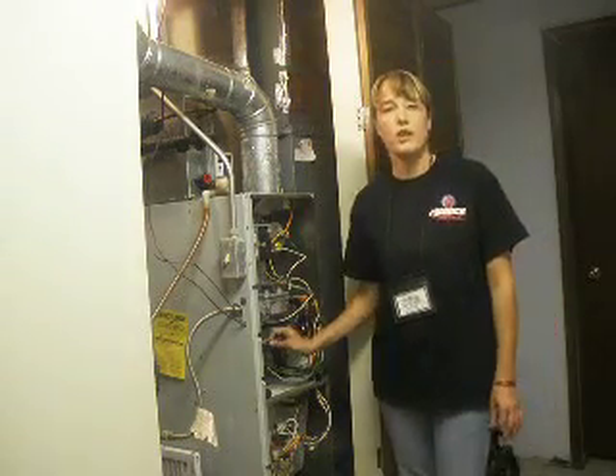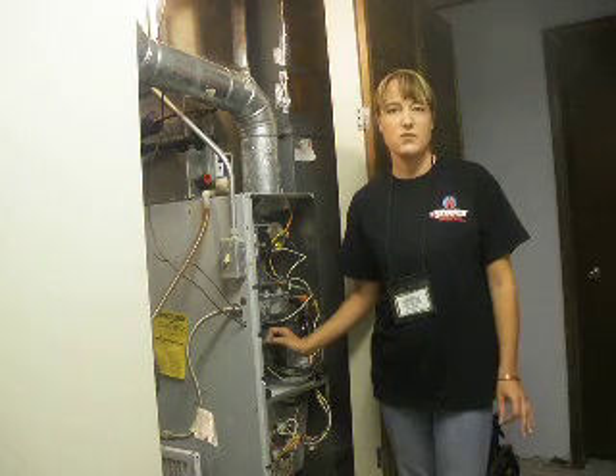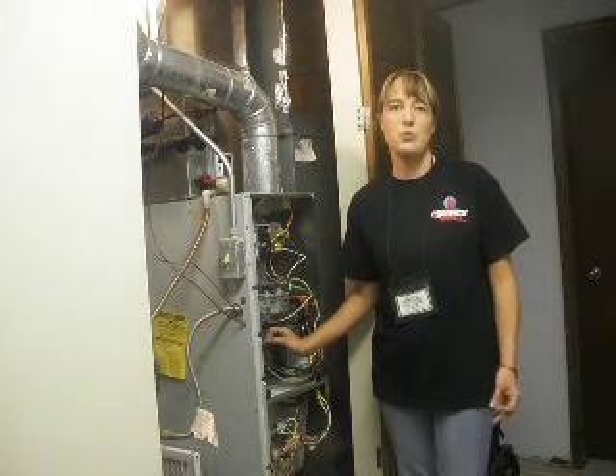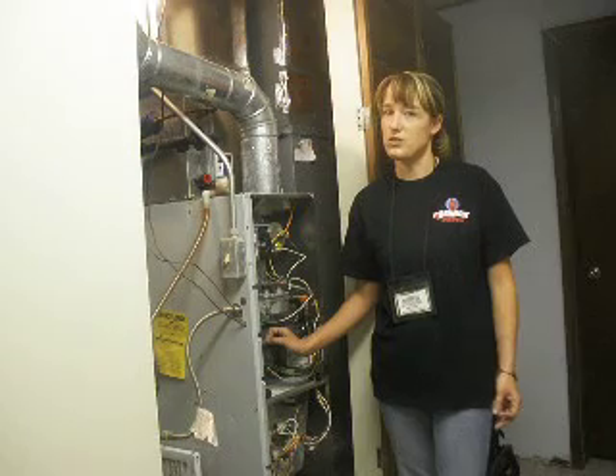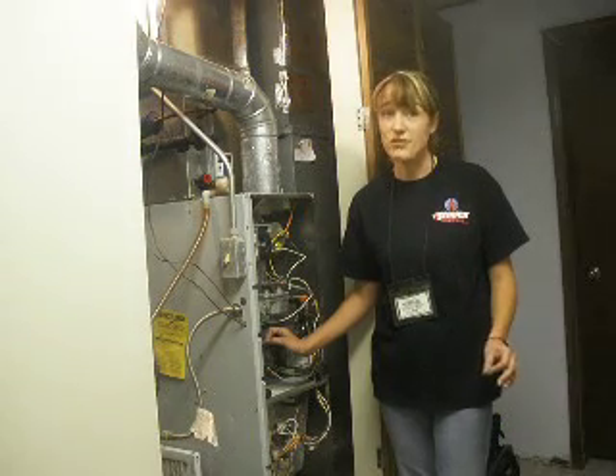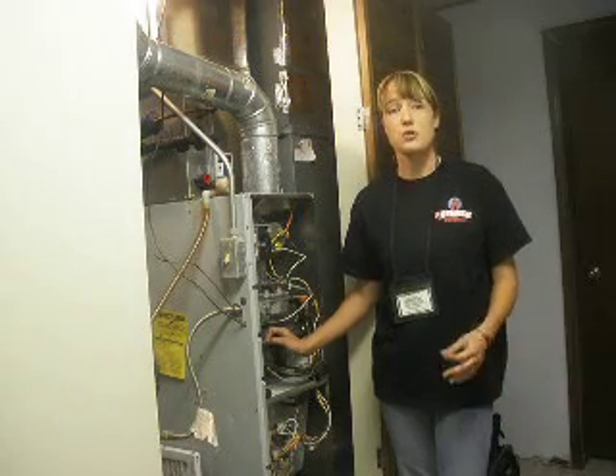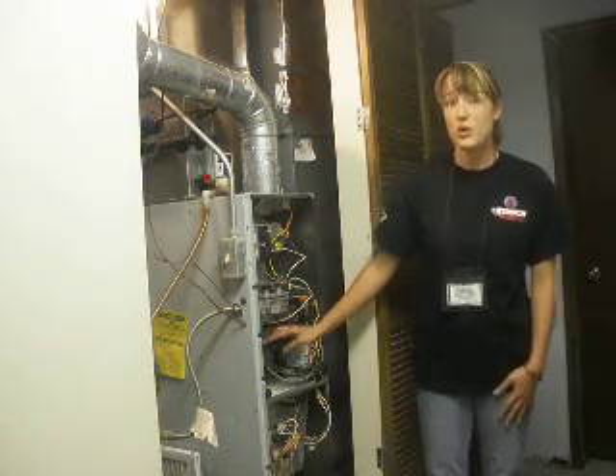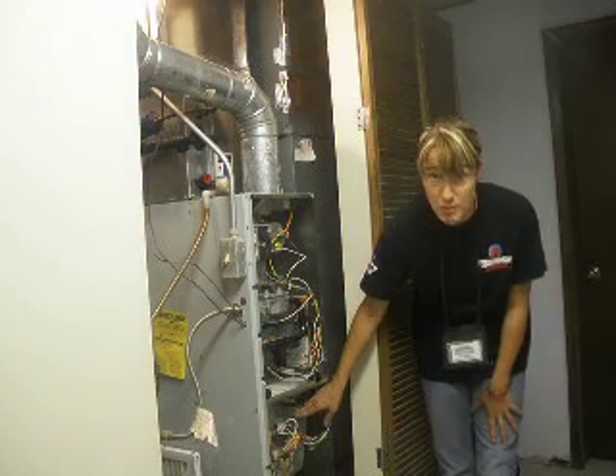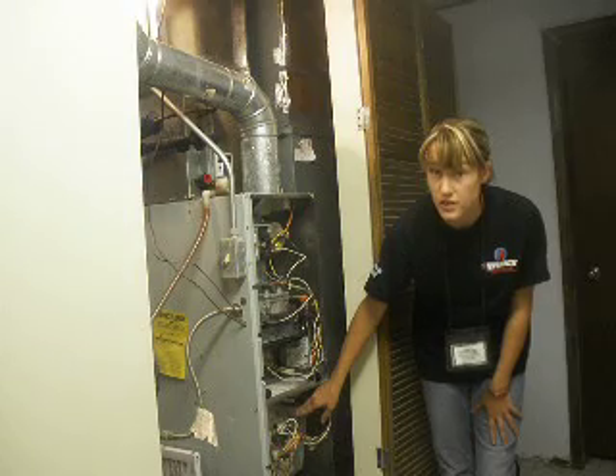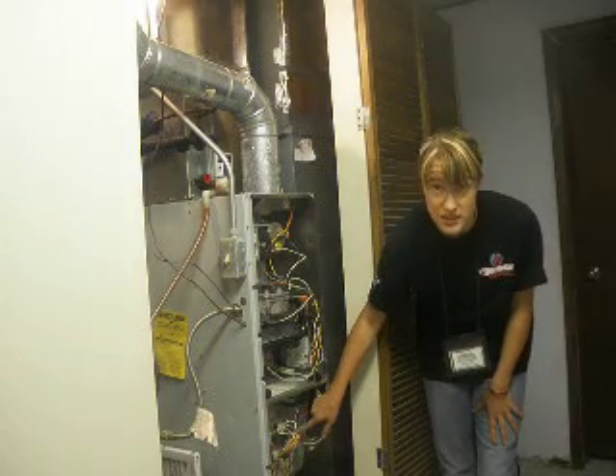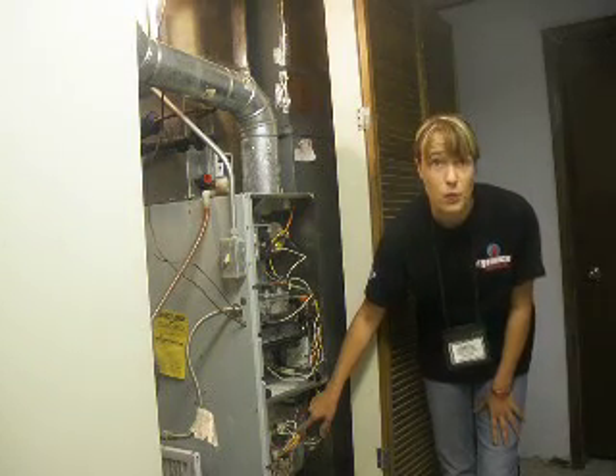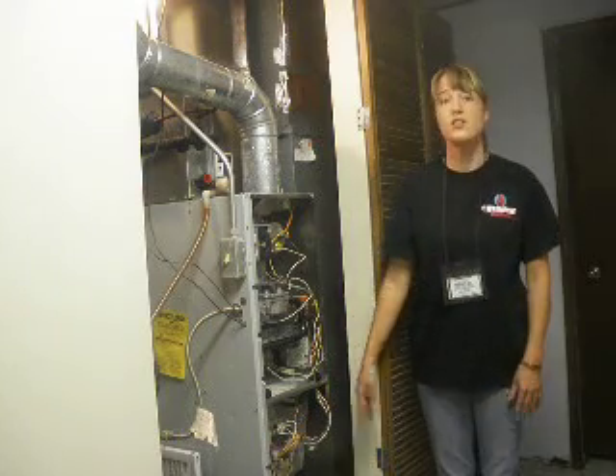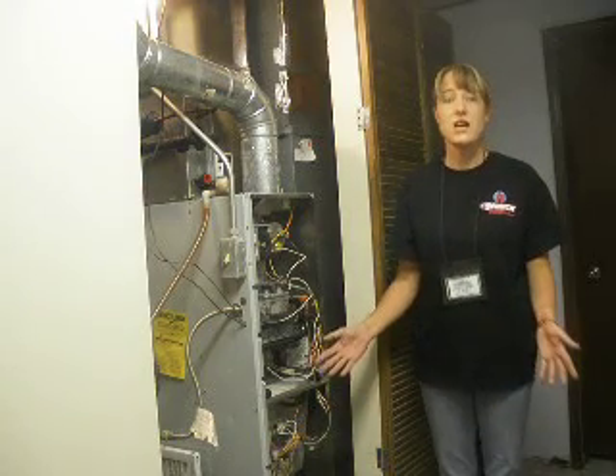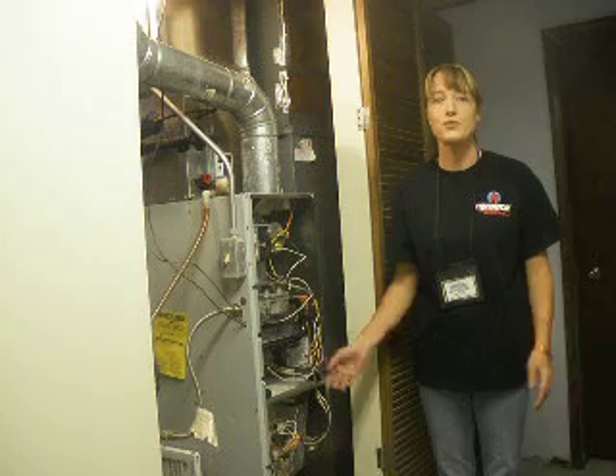Now, when most people were giving up their older, larger-sized gas furnaces, their biggest concern was the temperature of air coming out of the register. We have no control of the temperature of air that's going to be distributed. So the fan or the blower is not controlled by temperature, but by an integrated circuit here, all in the logic center. That circuit will control the blower to start. The furnace continues to operate until the thermostat is satisfied.